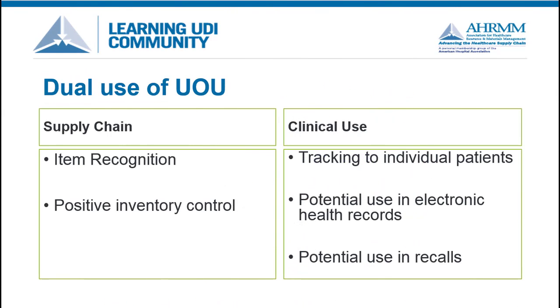We need to clearly differentiate the tracking of the packaged product, which is common to supply chain activity, from tracking the products which may be contained within those packages. When there are multiple devices contained in the lowest packaged level, there may be a need for clinicians to track the use of individual items on specific patients. The FDA created the Unit of Use concept to cover this precise need.